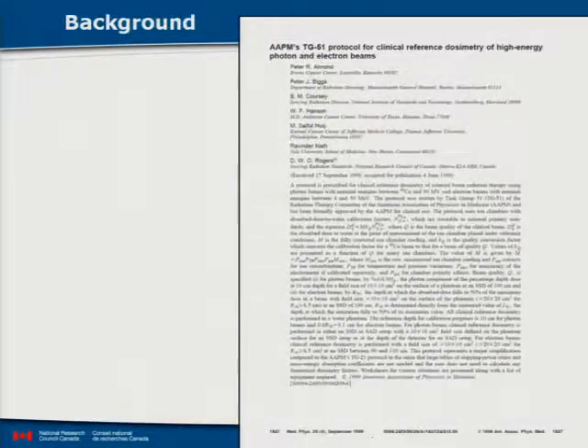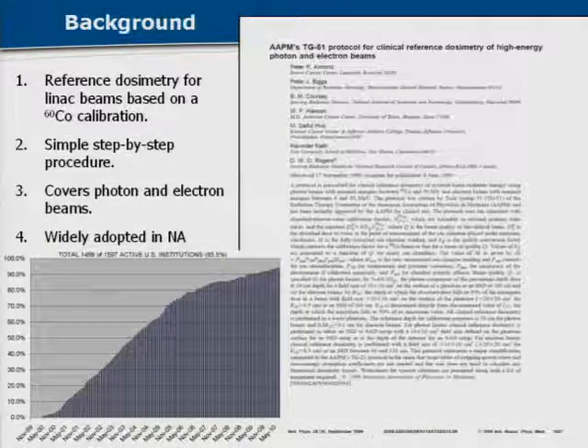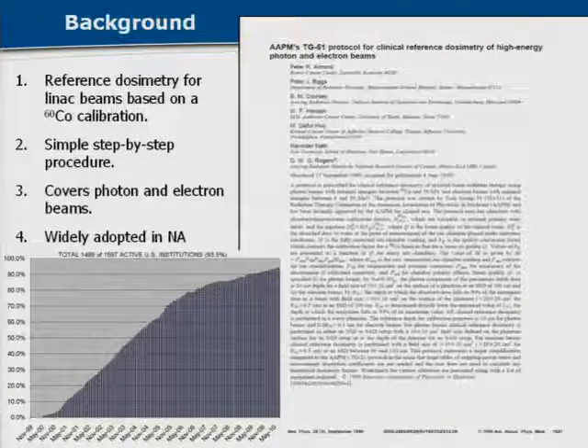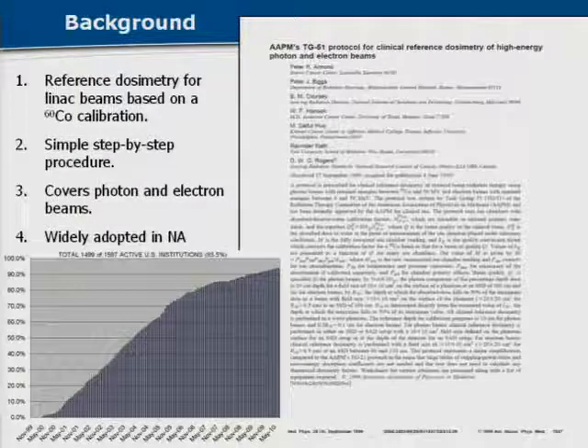So back to more serious business. This is what we're talking about — the AAPM TG51 protocol. Dave's covered it. I'll just highlight the bottom point: it's been widely adopted in North America since its inception. This is data from the RPC, and you can see that as of last year, 94% of institutions in North America are using TG51. So it's the protocol people are using, and it's legitimate to ask what we need to do next.